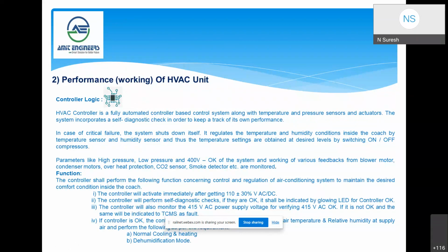These are more about the control logic. The microprocessor controller has all digital inputs, outputs, analog inputs and outputs. There are temperature sensors: supply air temperature, return air temperature, and fresh air temperature. Three sensors are available, and based on the input signal from the temperature sensors, the microprocessor will control the motors and the compressors. Basically, if parameters like high pressure, low pressure, and voltage are okay, then the system will function in a sequential manner.